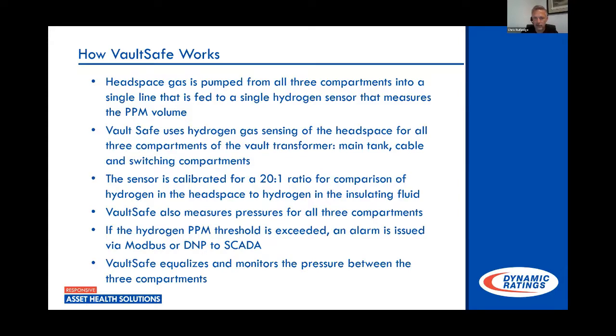monitoring is located. And then you also have to remember this hydrogen, it's steadily trying to escape into this gas state. So it's crossing that gas oil partition, and you're getting a very high concentration of it in the headspace of that transformer. Again, about 20 times more than what you would see dissolved in oil if equilibrium is reached in that transformer.